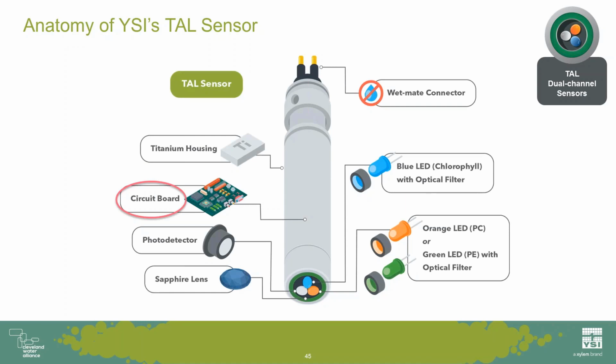So if a board is designed using older methods, or frankly, if it's just not very well designed, fortunately for me, we have some of the best board designers here at YSI, that car engine is idling higher and the noise is higher. This makes it a lot harder for the sensor to know what the real signal is that is coming through the board via the photodiode.